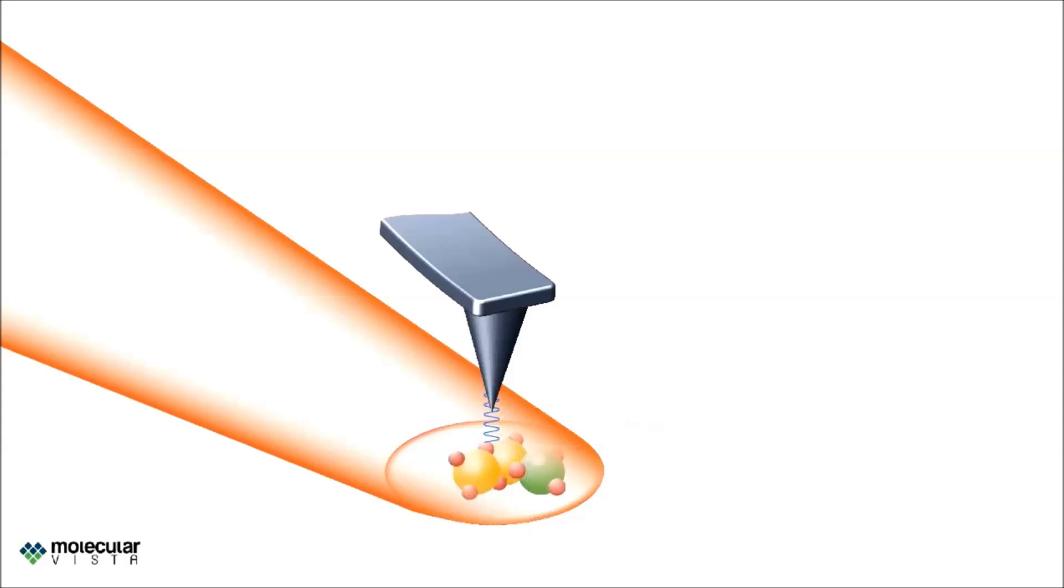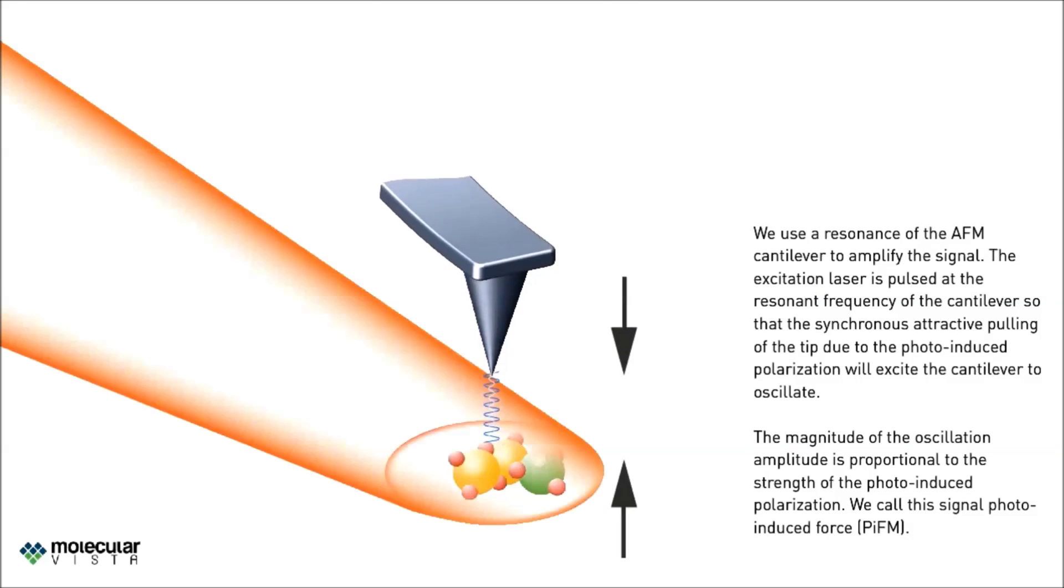We use a resonance of the AFM cantilever to amplify this small signal. To do so, we pulse the excitation laser at the resonant frequency of the cantilever so that the synchronous attractive pulling of the tip due to the photo-induced polarization will excite the cantilever to oscillate. The magnitude of the oscillation amplitude is proportional to the strength of the photo-induced polarization.